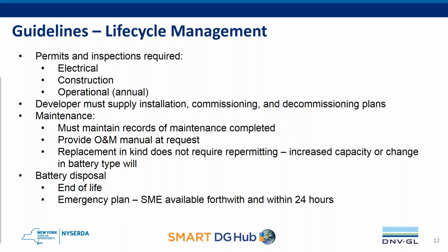So having a subject matter expert available, specifically within 24 hours available on site if necessary, and available to be called at all hours. For maintenance, although FDNY and Department of Buildings are not looking to dictate how the system is maintained, as we understand all systems have a little bit of different standards, you do have to maintain records of the maintenance that's completed.